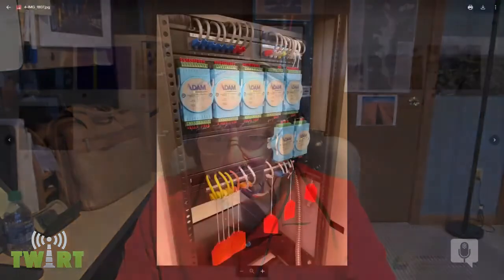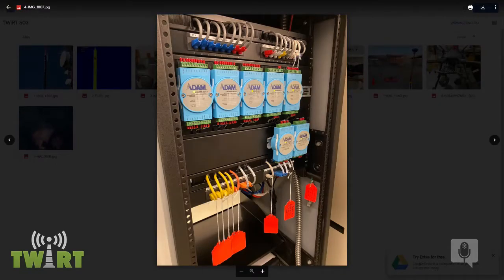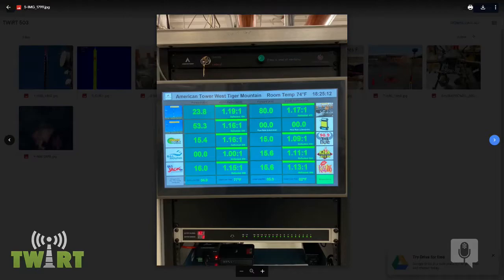We've got a picture there of the display. Well, yeah, I can describe this. This is where all the connections come back to from all those couplers in the previous picture. Those DC samples come back to these modules, called ADAM modules. They're data acquisition modules that measure the precise DC voltage, and the computer then reads that information off of an RS-485 bus, does all the calculations, and displays it on a screen. So this is basically the system. This is the rear of the rack you're looking at, and all those Cat 5 cables you see are the wires from all the sensors going around.